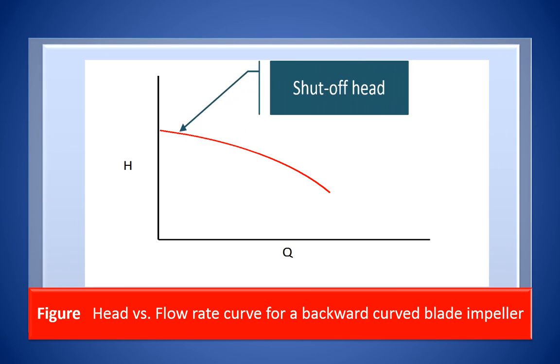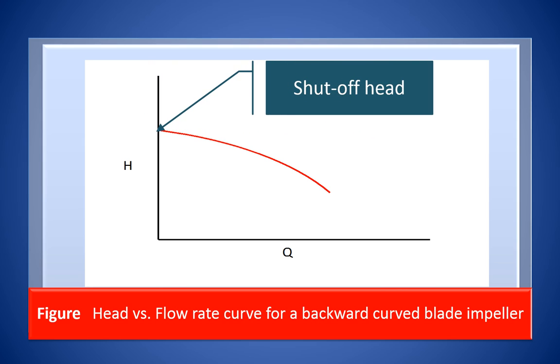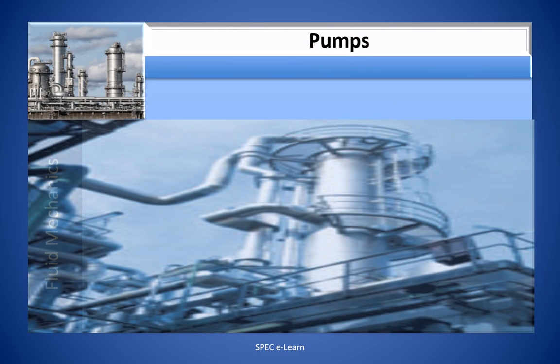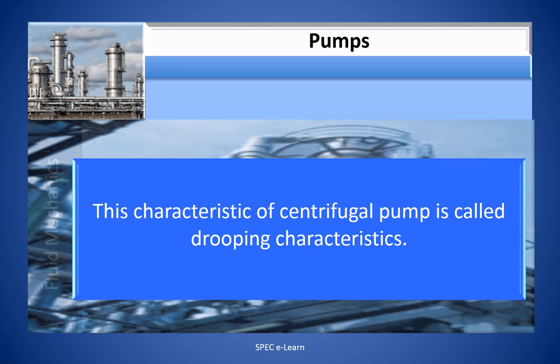Illustrated in this figure is the head versus flow characteristics of the centrifugal pump. Note that the head is maximum when the flow is zero. As the flow is increased, the head drops. This is a graphical representation of the mathematical expression for the head rise we discussed earlier. This characteristic of a centrifugal pump is called drooping characteristics.